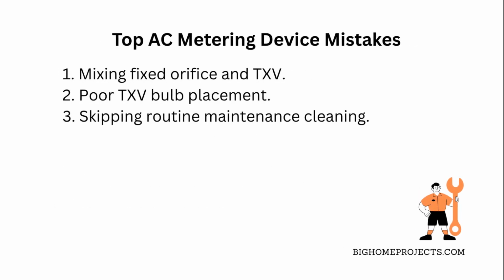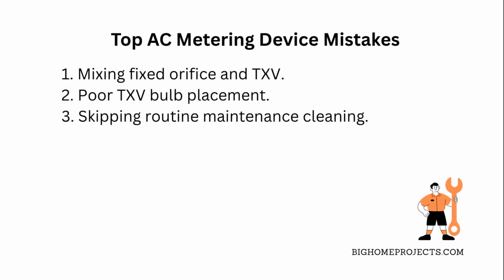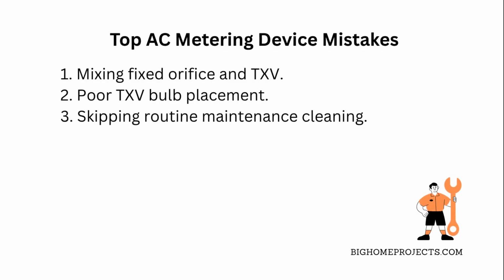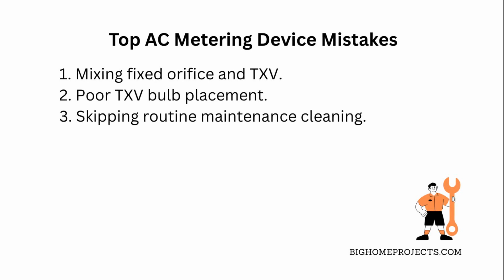One of the biggest mistakes with AC metering devices is mixing up fixed orifices with thermostatic expansion valves during replacement. This can cause poor cooling or even damage your system. Fix that by always matching the exact type specified for your unit.